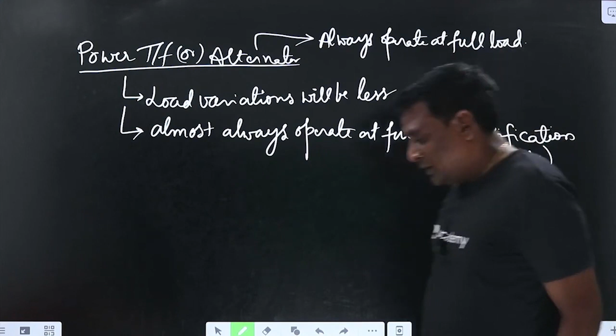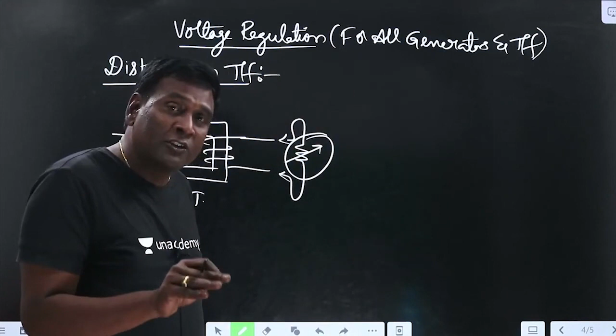Now, the definition of voltage regulation: no load to full load only should be defined for a power transformer. No load to full load voltage variation only should be defined for an alternator. But in a distribution transformer, voltage regulation should be defined from no load to any load.